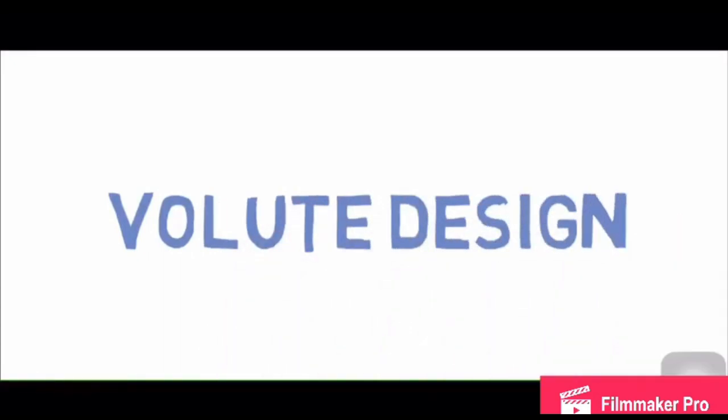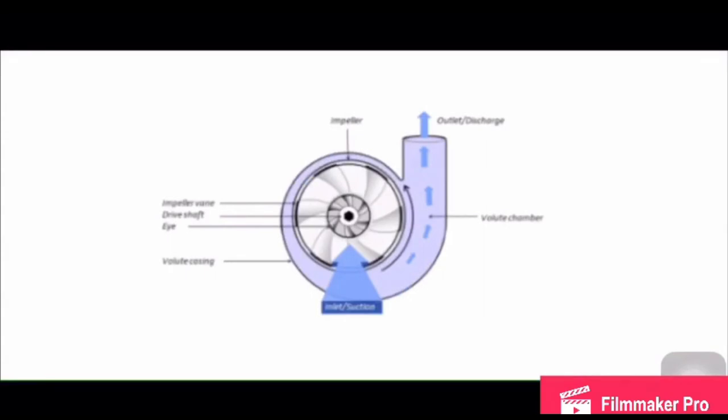For volute design, the impeller offset creates a curved funnel with an increasing cross-sectional area towards the pump outlet. This design causes fluid pressure to increase towards the outlet.